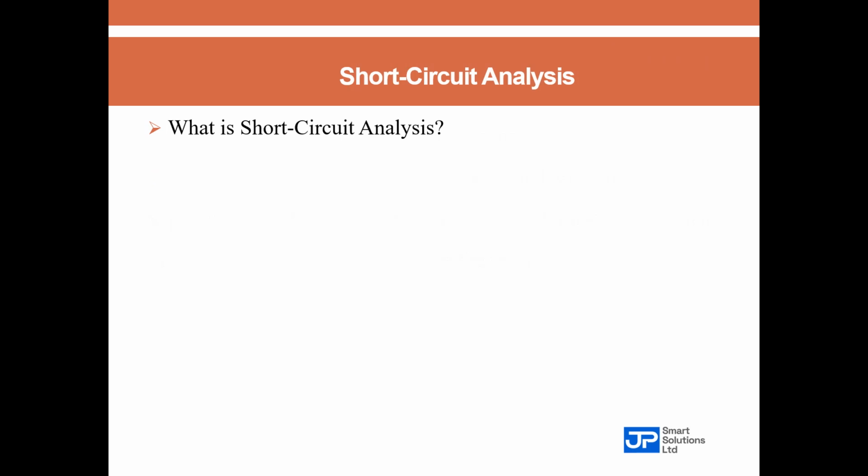Yet, I've seen too many engineers rely on rule of thumb breaker sizing or copy paste specs from old projects without ever checking if those breakers can actually interrupt the actual fault current. Now, this is engineering malpractice. Yes, engineering malpractice. So then, what is this short circuit analysis really about?